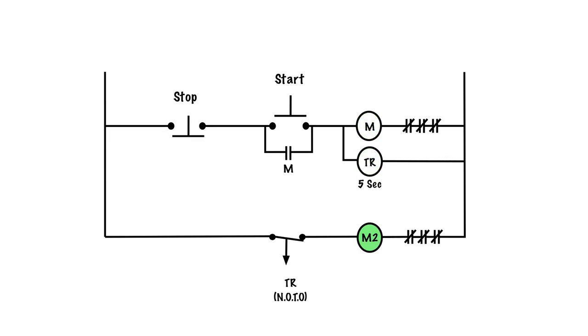When I hit the stop button, it de-energizes the circuit. The stop button pops back into place, M is de-energized, TDR is de-energized — and this is where the timing begins. Five seconds after TDR de-energizes, the timed contact will open, so M2 will run for five seconds and then shut down. The sequence: when we start, M energizes, TDR energizes, and M2 energizes. When we press stop, motor M stops instantly and motor M2 stops five seconds later. That is how an off-delay relay is used in a motor control circuit.